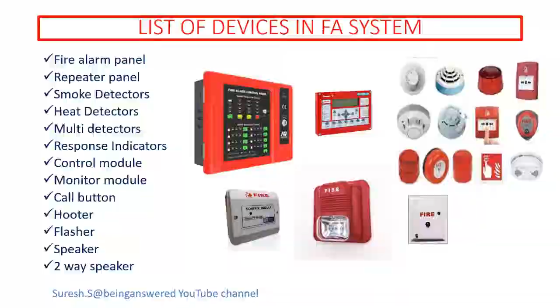It should have inbuilt battery backup so that even in failure of power, this panel can communicate with the devices. Spare loop cards to be considered so that in any critical situation, if the loop card fails, the other loop card can be a backup. Number of devices connected in one loop should be 80% of the capacity. Similarly, the length of the wire should be used only 80% of the maximum capacity. In general, 125 devices can be connected in one loop and 1200 meters of wire can be connected in series.